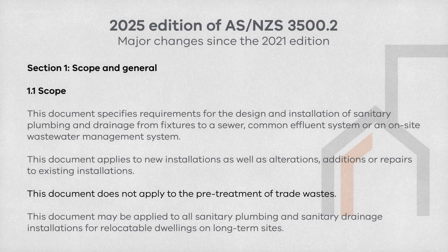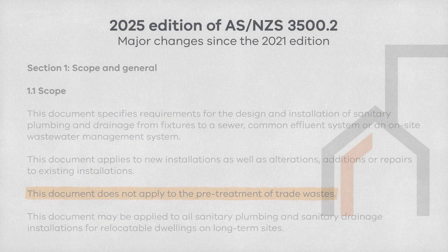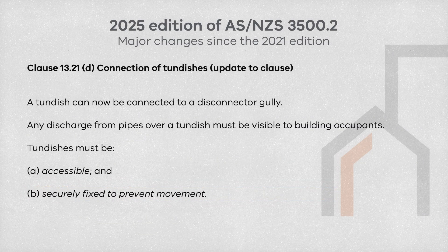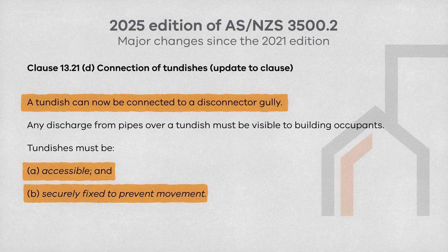Firstly, clause 1.1 has been updated where the informative note from the previous standard has now been incorporated into the 2025 standard. Plumbers should now coordinate with the network utility operator regarding the requirements for pre-treatment of trade wastes. Clause 13.21 has now been updated to allow a tun dish to be connected to a disconnector gully. Tun dishes must also be accessible and securely fixed to prevent movement.